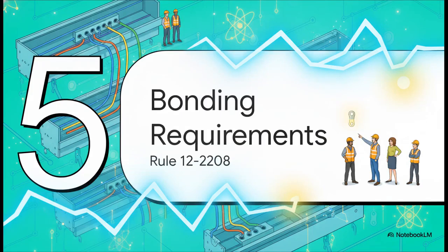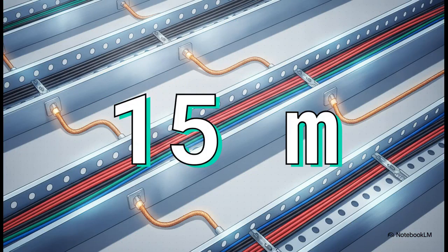Next up, Section 5, Mandatory Bonding Requirements. We are looking at Rule 12-2208 here. I honestly cannot stress this enough. Bonding is one of the most critical safety concepts for your Red Seal exam and, more importantly, for human life on site. 15 meters. Commit this number to memory right now. Except in a few very specific situations, metal cable trays shall be bonded at intervals not exceeding 15 meters. And remember, the size of your bonding conductor is based on the ampacity of the largest ungrounded conductor in the tray, as per Rule 10-616.